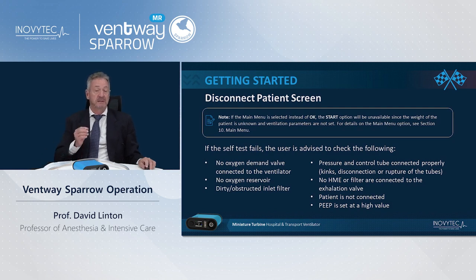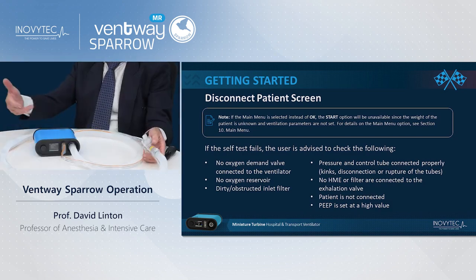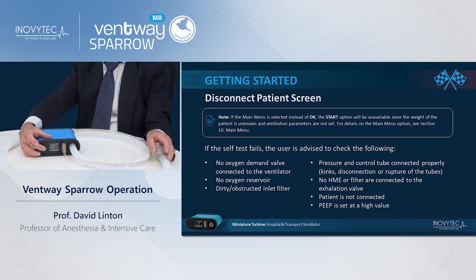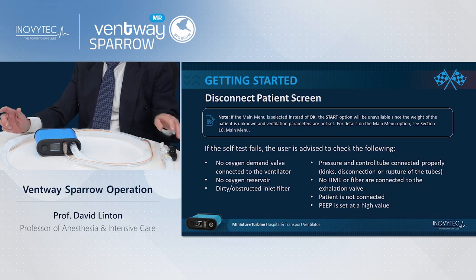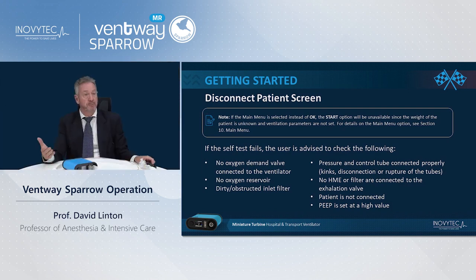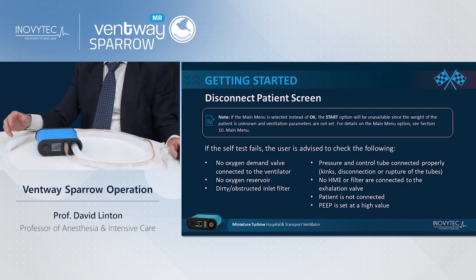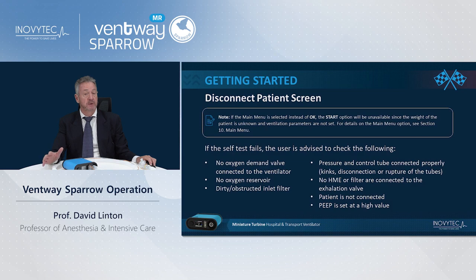These filters can have a little bit of resistance, and the machine recognizes that and says that the circuit is not intact. So make sure the circuit and tubes are connected properly, there are no kinks, disconnections, tube rupture or injury to the tubes, and there are no filters or HME connected. Once you see the sign on the screen, you simply click on the button, and in 12 seconds it will go through the process and do the circuit verification test. Then the ventilator is ready for use.